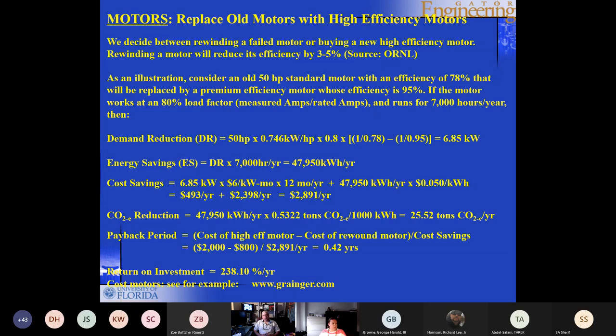So here, what we do is we replace. We have to make a decision as to whether we should rewind the failed motor or buy a new premium efficiency motor, or a high efficiency motor. The difference between a high efficiency motor and a premium efficiency motor is a very small increase in the efficiency. I believe 96% for the premium efficiency, 95% for a high efficiency.